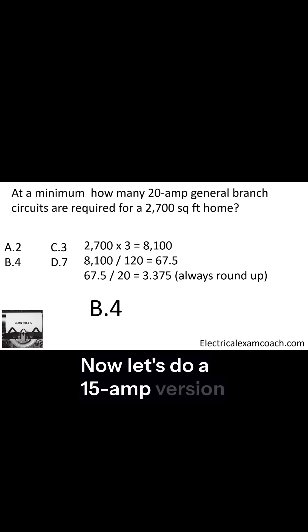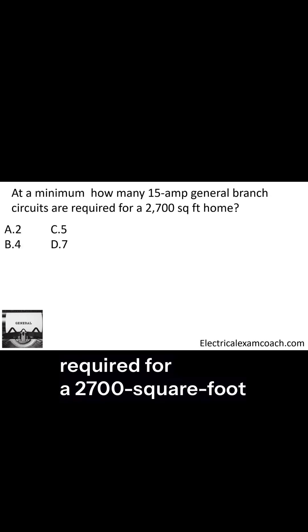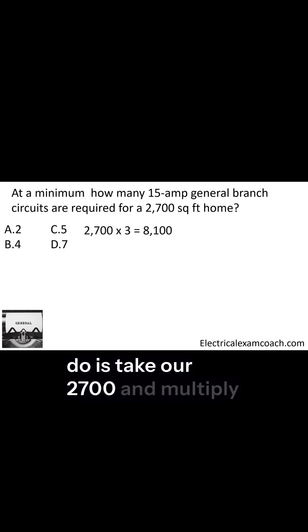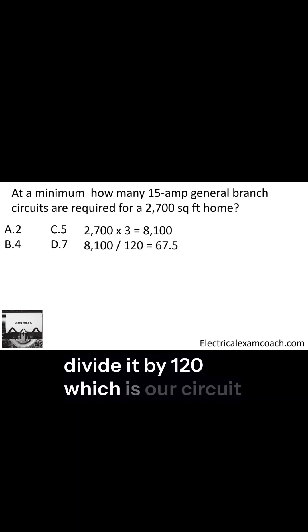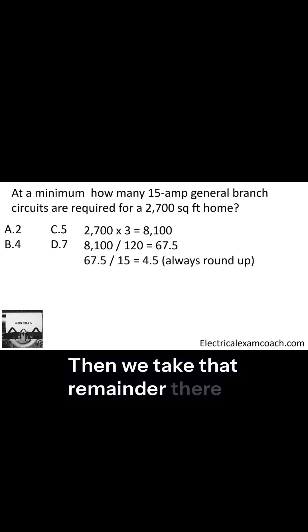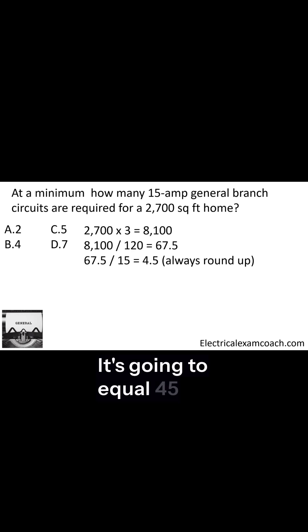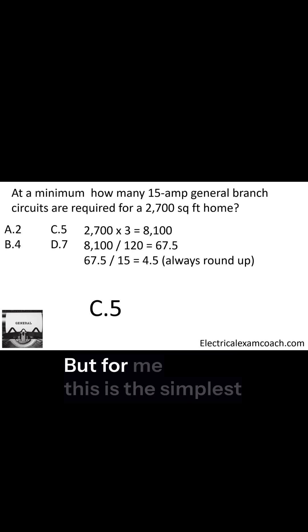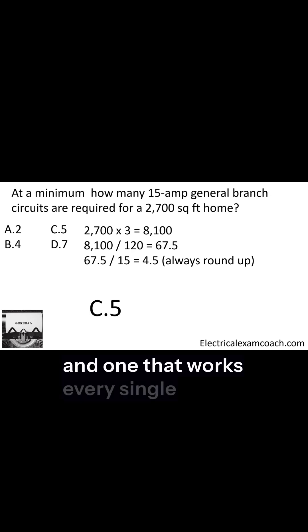Now let's do a 15 amp version. At a minimum, how many 15 amp general branch circuits are required for a 2700 square foot home? The first thing we're going to do is take our 2700 and multiply it by three VAs per square foot. Then divide that by 120, which is our circuit voltage. Then take that remainder and divide it by the size circuit — in this case, 15 amps. It's going to equal 4.5, and we always round up to five. There are other ways to calculate this, but this is the simplest method that works every single time.